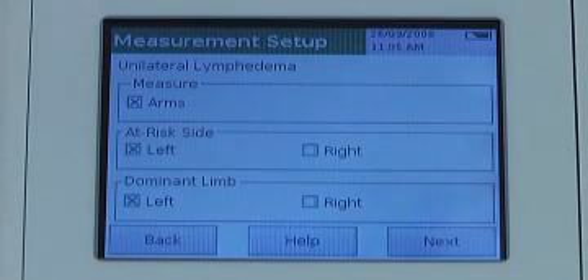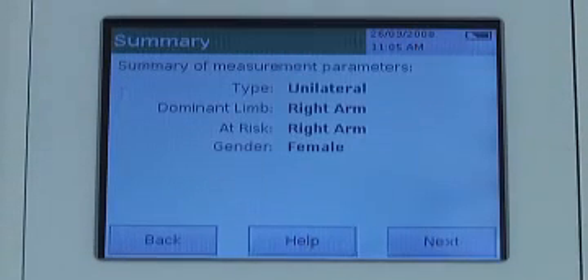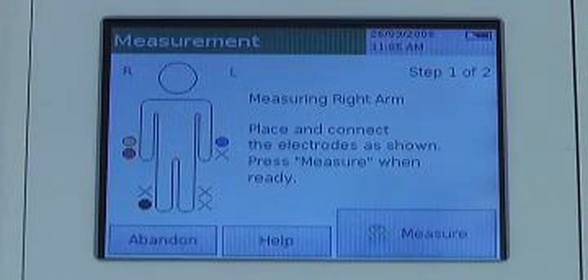The next screen will ask you to confirm your entries. Once you have confirmed your entries, press OK. The next screen will ask you to enter information regarding the patient's dominant and at-risk arm status. Once parameters have been entered, press Next. The next screen will ask you to confirm your entries. Once you have confirmed the measurement parameters, press Next. At this point, the device will prompt you to begin the measurement process. You will be taking measurements of both arms. Regardless of the at-risk arm, the right arm will always be measured first.